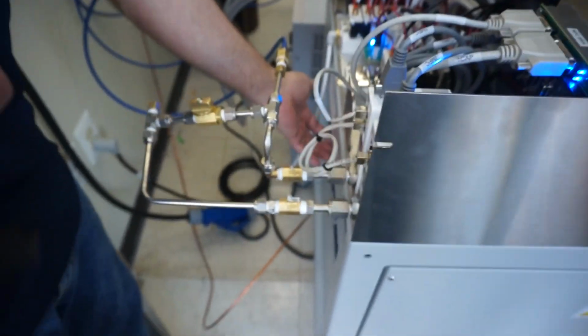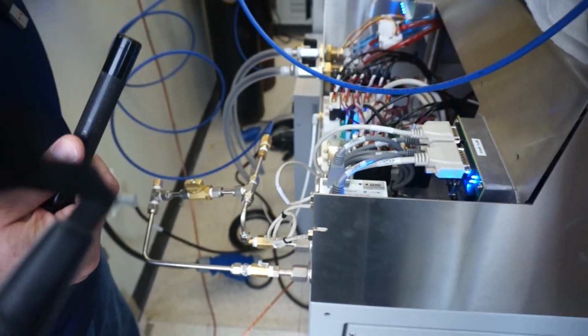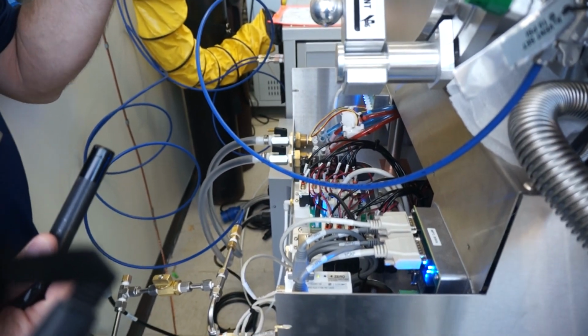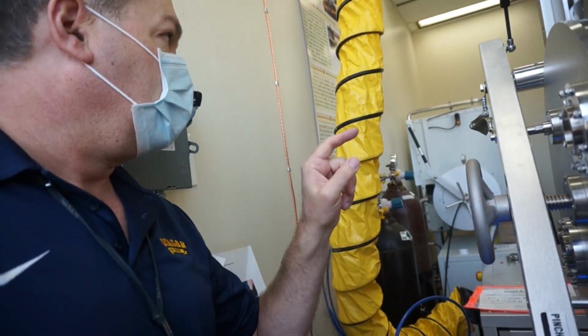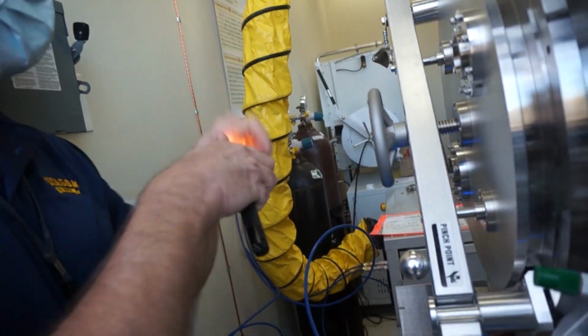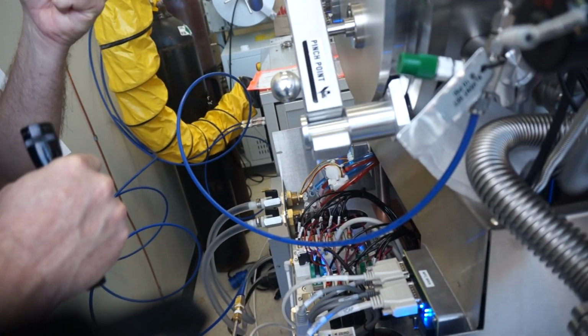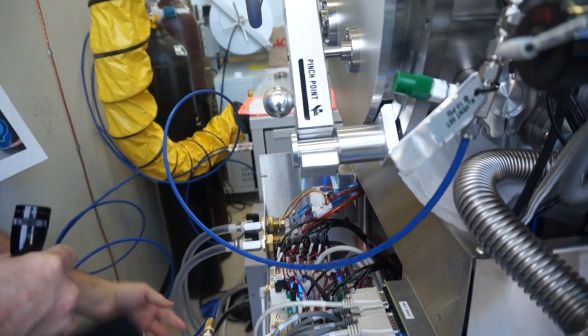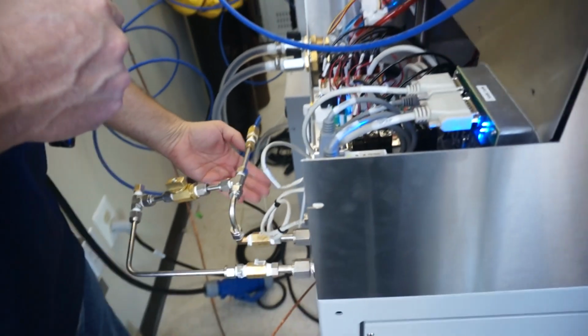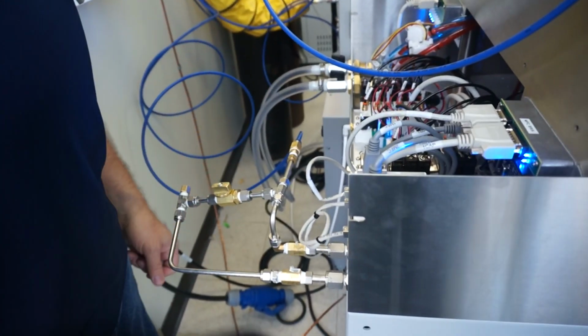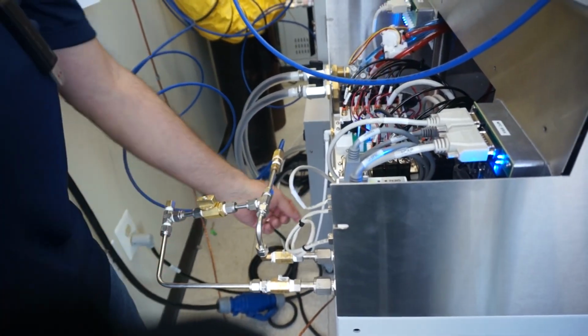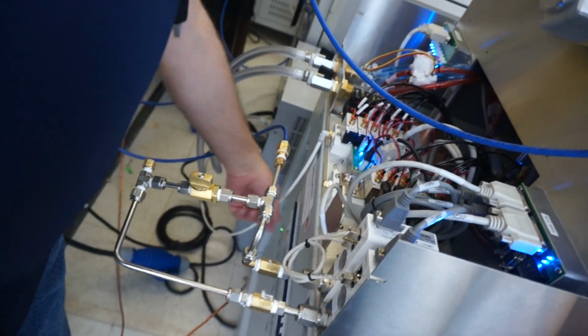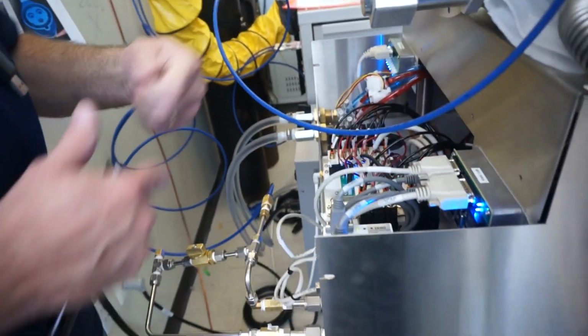But if I took this panel off on the bottom of this unit, there is an IEC connector. It kind of looks like a goofy computer plug that's square and rectangular and has the corners cut off. It's a female socket. Right. And they go to the respective circuit breakers. So I don't know what your lockout tagout program is. Worst case, you know, we actually do sell circuit breaker locks, or you could just pull the plug out and put a cover over top of it.